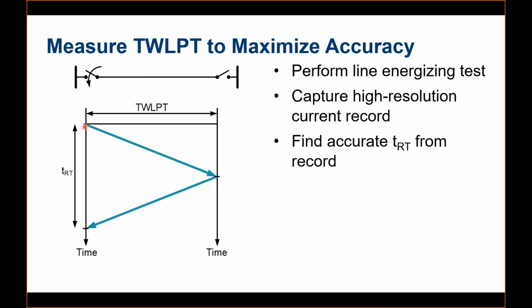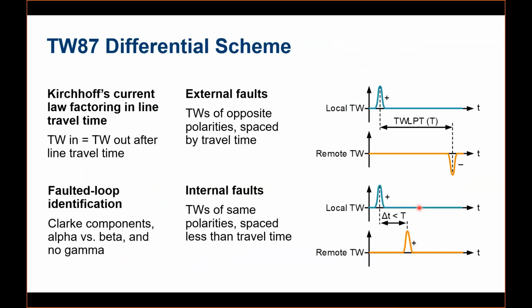The time taken by the traveling wave to travel from this end and come back is called the round trip delay. If we divide that round trip delay by two, we can easily find the time taken by a traveling wave to travel from your local station to the remote station. So this parameter, TWLPT, can be measured much more precisely with this test. If you cannot do that, there is the previous method you can use to estimate it as well. This information is also required to calculate a very precise fault location. All right. The first element that we're going to discuss is a differential element that is based on traveling waves.